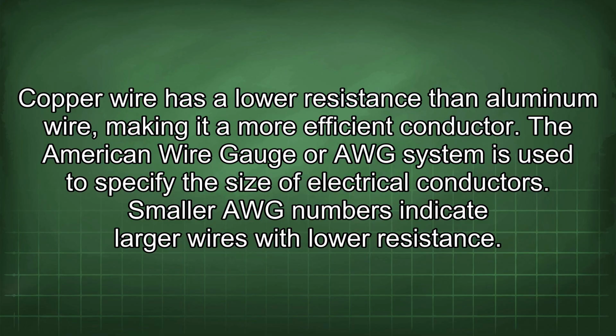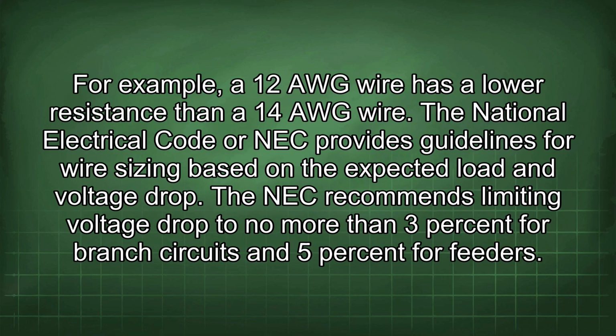The American Wire Gauge, or AWG, system is used to specify the size of electrical conductors. Smaller AWG numbers indicate larger wires with lower resistance. For example, a 12 AWG wire has a lower resistance than a 14 AWG wire. The National Electrical Code, or NEC, provides guidelines for wire sizing based on the expected load and voltage drop. The NEC recommends limiting voltage drop to no more than 3% for branch circuits and 5% for feeders.